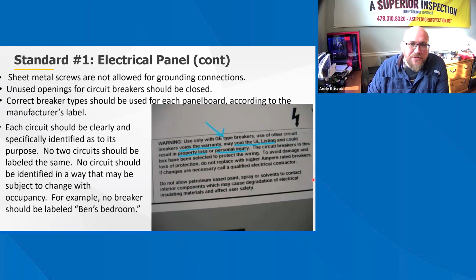Correct breaker type should be used for each panel board according to the manufacturer's label. And each circuit should be clearly and specifically identified as to its purpose. No two circuits should be labeled the same. No circuit should be identified in a way that may be subject to change with occupancy. For example, no breaker should be labeled Ben's room.